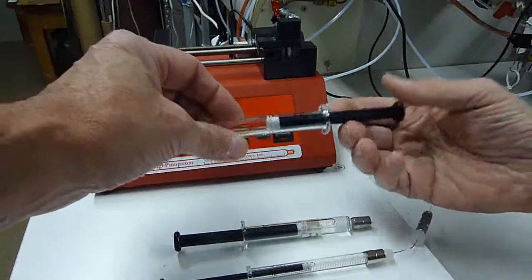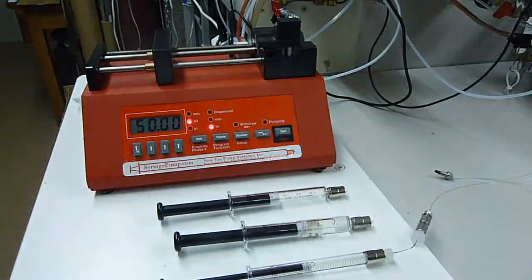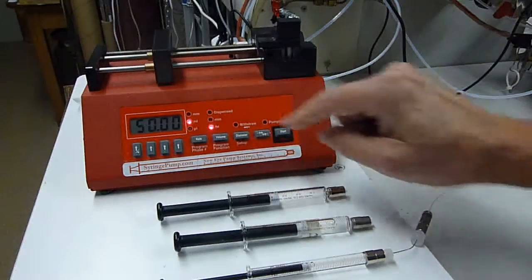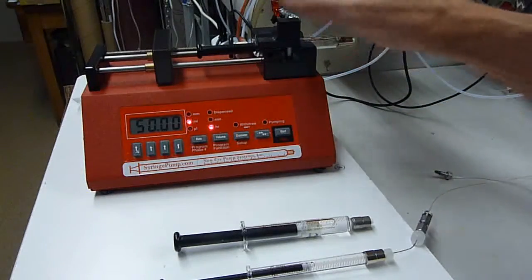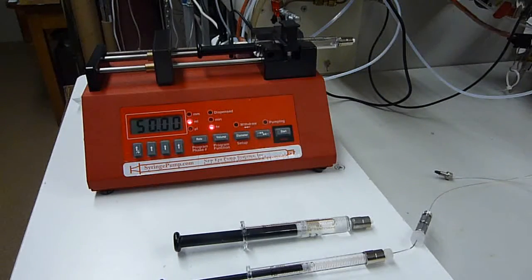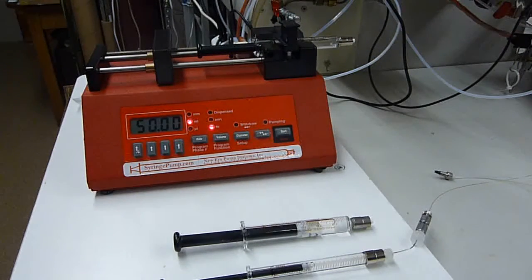Both the 5 ml and the 1 ml gas-tight syringes have the same displacement length, so if I set up the controls for a 5 ml syringe flow, if I swap syringes I don't bother changing the display in the diameter. I just know to divide the display by 5—that is, 1 fifth of the flow is what the syringe is actually going to deliver if I use a 1 ml syringe instead of a 5 ml syringe.